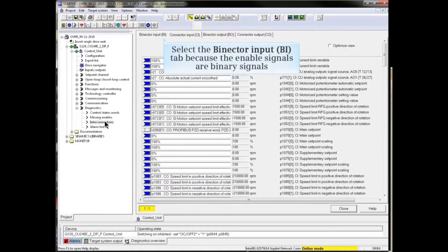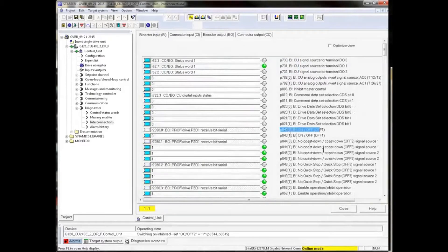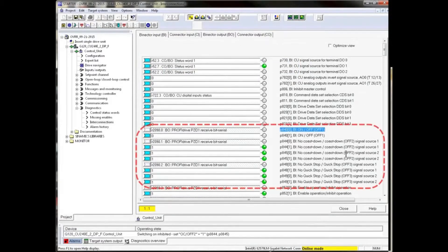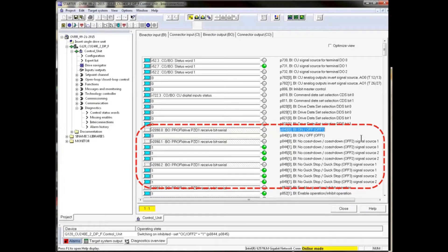Scroll down to p840, p844, 845, etc. and see that the signal source is from Static Highs or from the PROFIDRIVE signal on r2090.